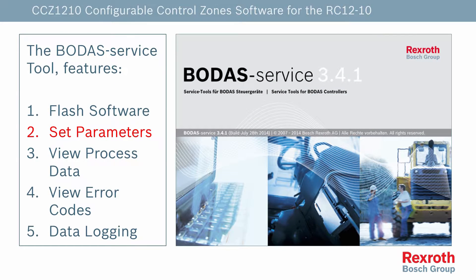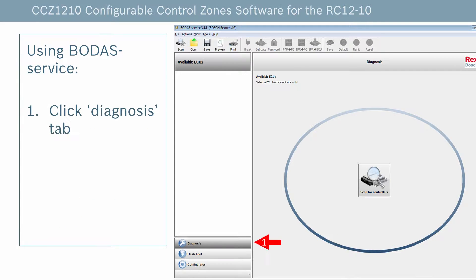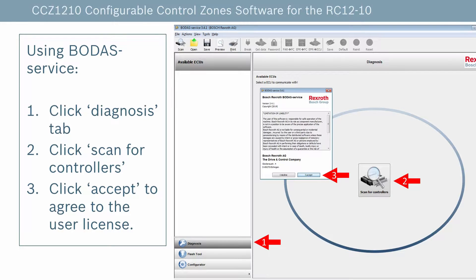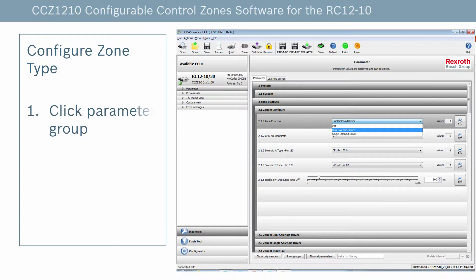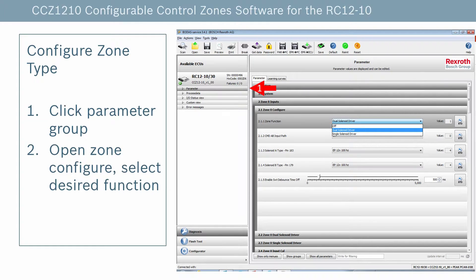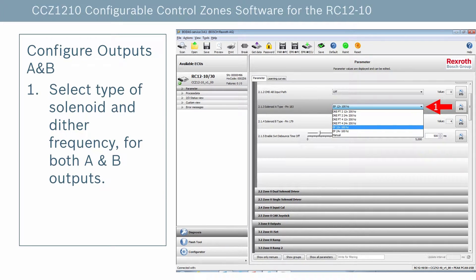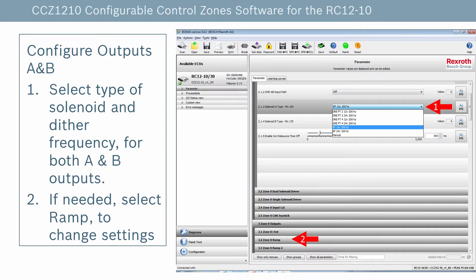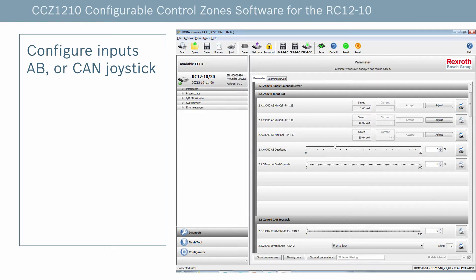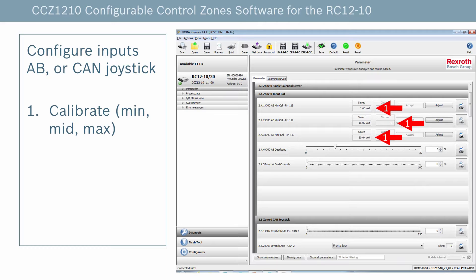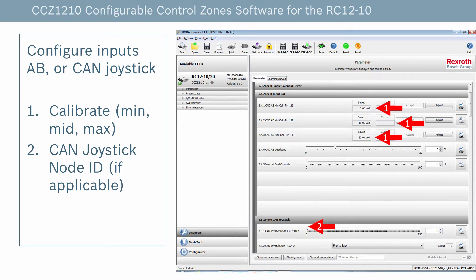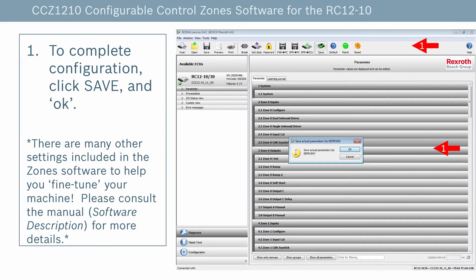To configure the zone parameters, we'll be using the Diagnosis portion of BODAS-service. First, click the Diagnosis tab, then click the Scan for Controllers button in the middle of the screen, and click to accept the license agreement. Once the service tool is connected to the zone program, click Parameter, then click Zone Configure, and then select the desired function. Next, using the drop-downs, configure the solenoid types for both A and B outputs. If needed, select the zone ramp to adjust the faster or slower speed. Finally, if an analog input is being used, select Input Cal to calibrate the input. However, select CAN Joystick and set up the Node ID for a CAN Joystick input. At this point, you're ready to click the Save button at the top of your screen with the green checkmark, and the parameters will be saved to the controller.